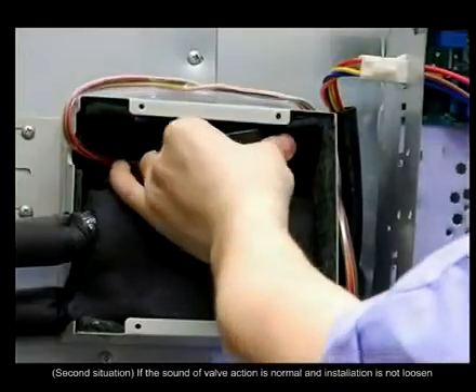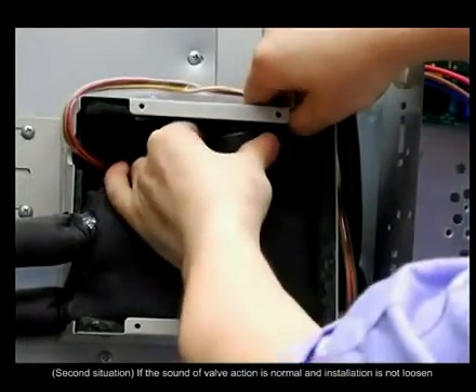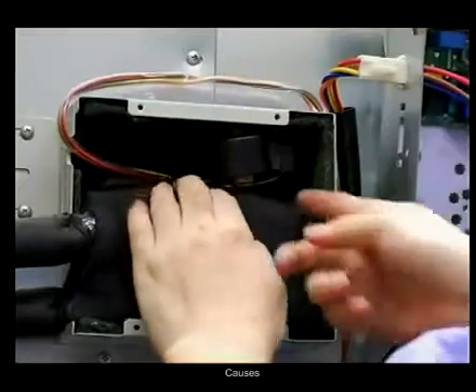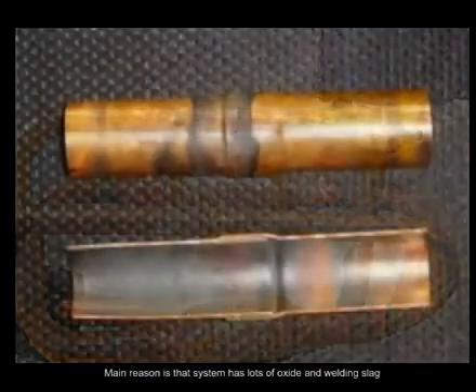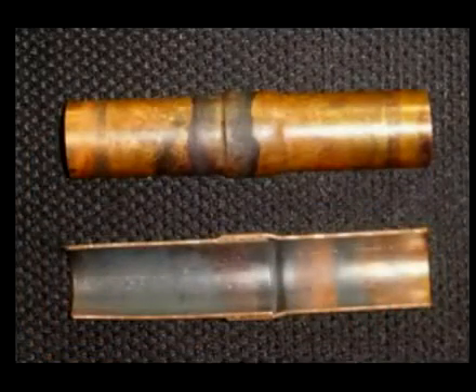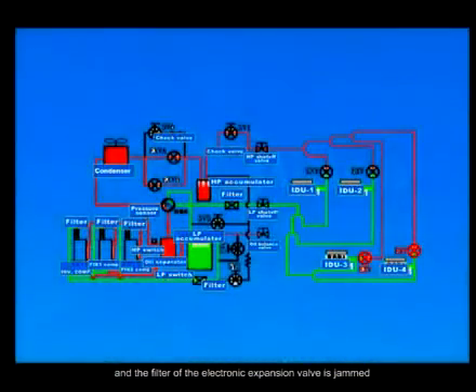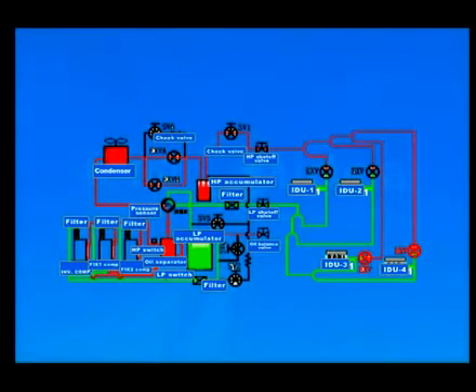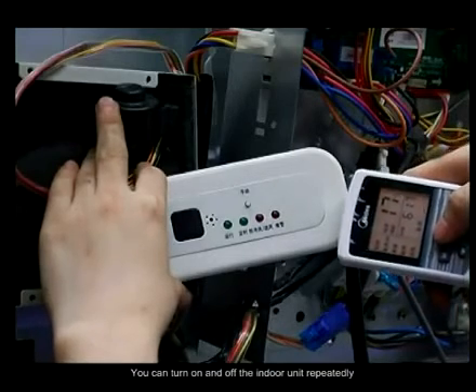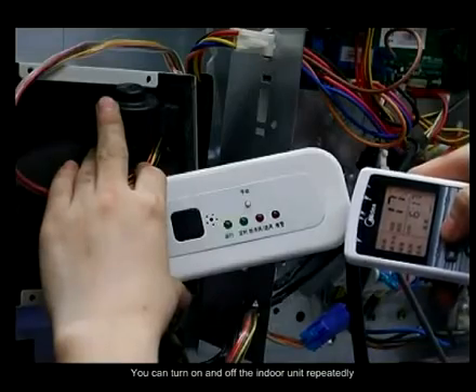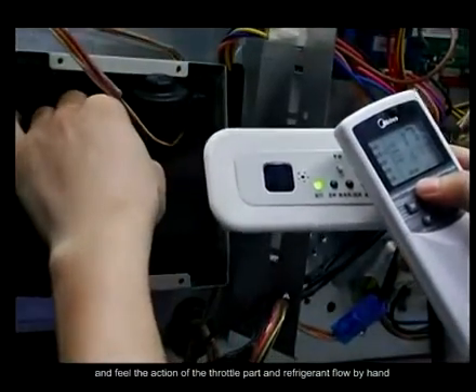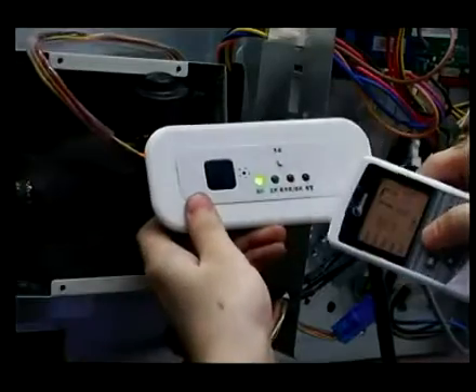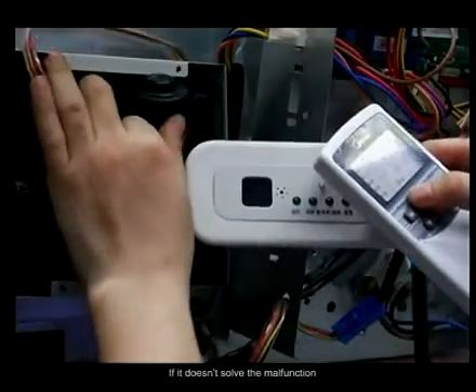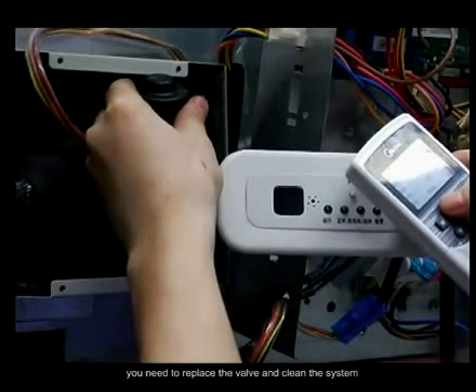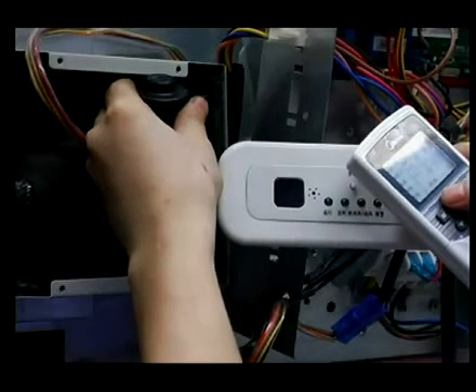Second situation. The sound of valve action is normal and the installation is not loosened. Causes. The main reason is that the system has lots of oxide and welding slag, and the filter of the electronic expansion valve is jammed. You can turn the indoor unit on and off repeatedly and feel the action of the throttle part and the refrigerant flow by hand. If it doesn't solve the malfunction, you need to replace the valve and clean the system.